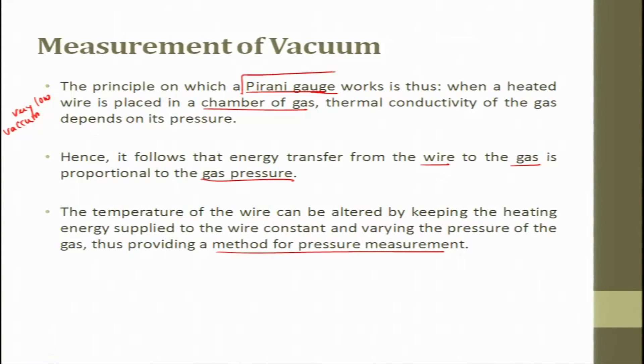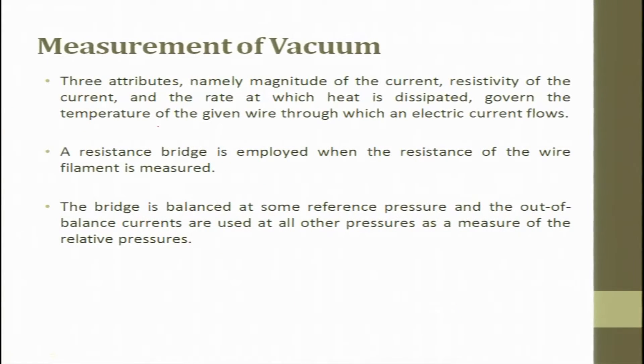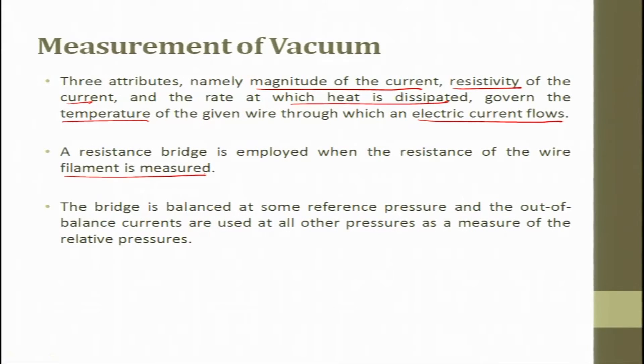This is one of a very important gauge which even now finds application. Three attributes — namely magnitude of current, resistivity of the current, and the rate at which heat is dissipated — govern the temperature for a given wire through which electric current flows. A resistance bridge is employed; when the resistance of the two filaments is measured, the bridge is balanced at some reference pressure and the out-of-balance currents are used at all other pressures as a measurement of relative pressure.